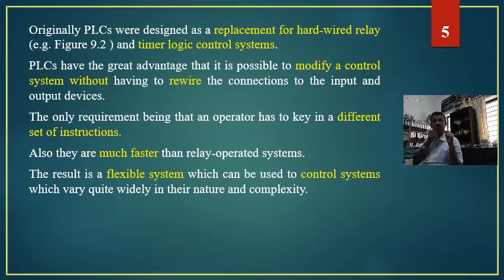And more than that, there is one more problem with the relay: whenever there is a switchover, it makes a noise because one contact needs to be broken and another contact needs to be made. If these contacts are at high voltage, it will lead to a spark. A spark will lead to wear. Wear will lead to replacement. These are some of the problems associated with the relay. That is why it is mentioned that PLCs are quiet.